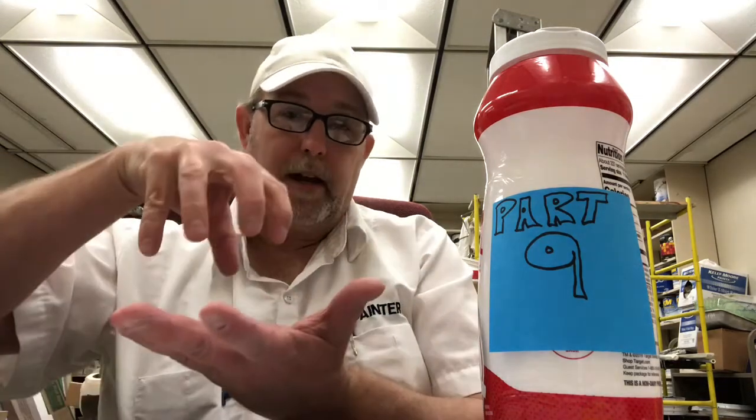You have your filter. You have some batteries with you in case a smoke alarm needs one. Oh, there's also water alarms that sit on the floor around the water heater in case it's leaking, or you've got a plugged up condenser line or whatever, and it starts beeping. So when the people hear that, they call and say there's something beeping inside my water heater area. So anyway, you check to make sure the batteries are good on that. You just put it on your hand. There's enough moisture in your hand for it to go off. So you check it. So check the smoke alarm.